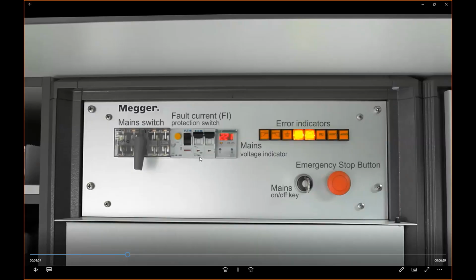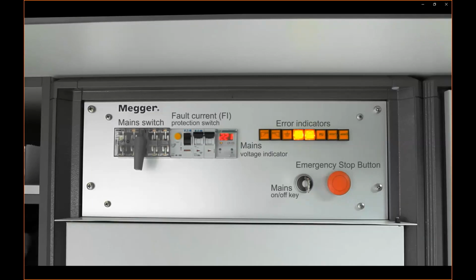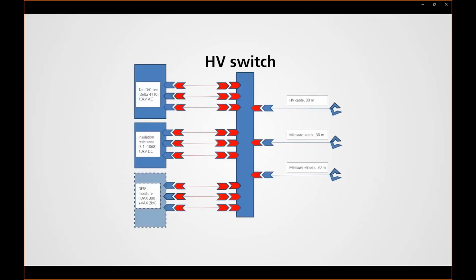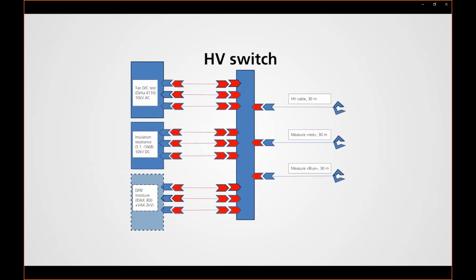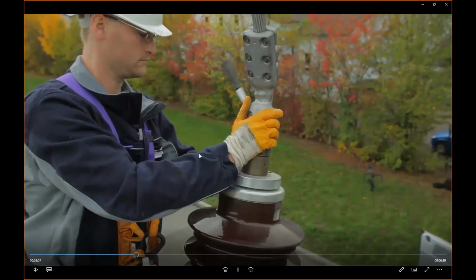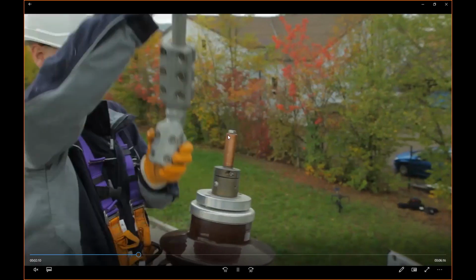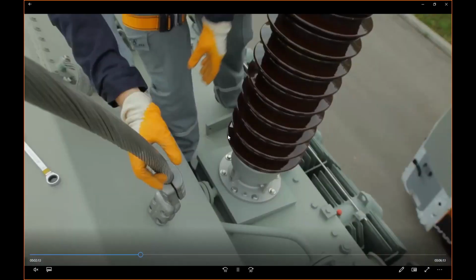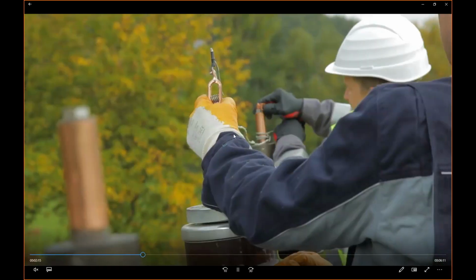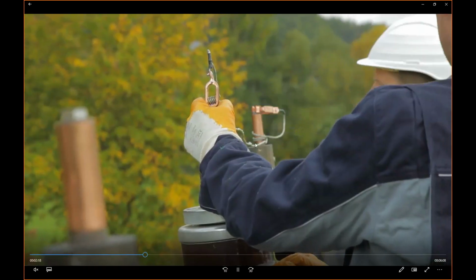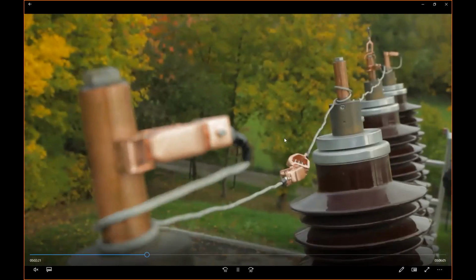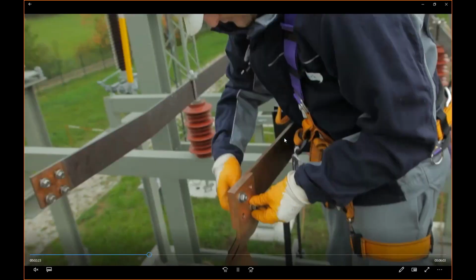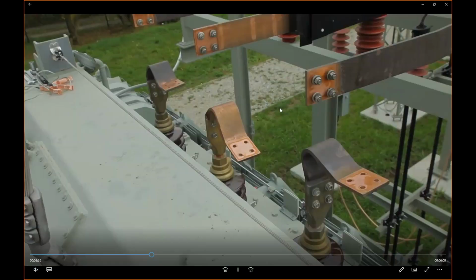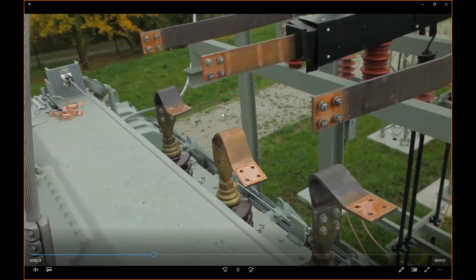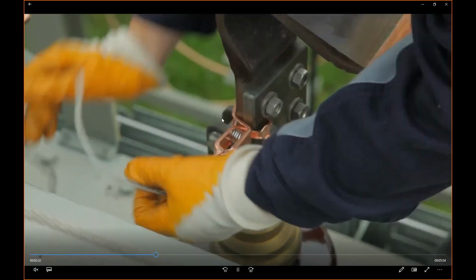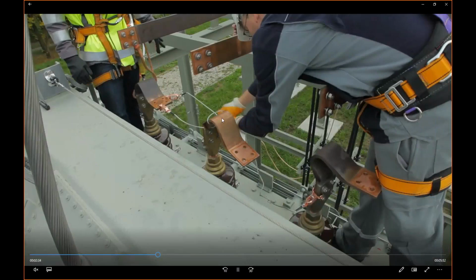In case the transformer is sitting in the building or not in an easily accessible location, you can take it out within a few seconds and operate on a standalone basis. So now we're removing the grid connection to the transformer. We're making the short where all three or four terminals in that case are interconnected. Same is happening to the low voltage side, where the bus bars are removed on the LV side, and we're making the short in this instance as well.